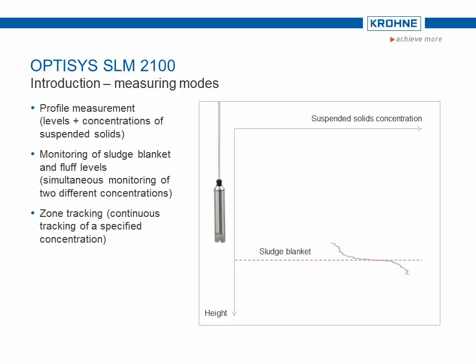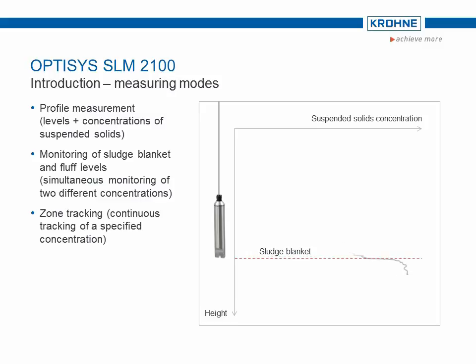With the third measuring mode, the zone tracking mode, a specific concentration level is continuously tracked. The sensor moves up and down slightly in the area of the particle concentration to be tracked and thus constantly identifies the current position of the target value. In this way, any change in the level — for example during de-pumping — can be continuously tracked.